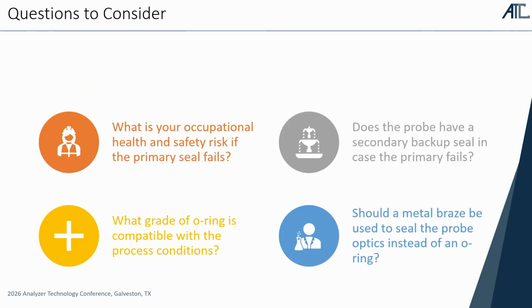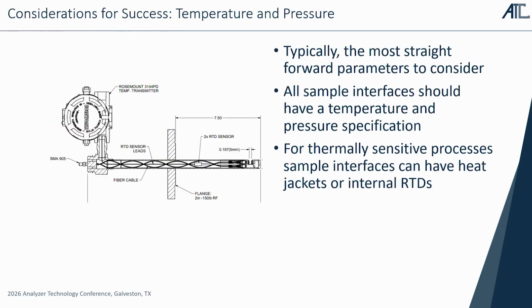But some questions to consider are like, what are the occupational health and safety risks if those seals fail, right? Does a probe have a secondary seal so if we do get a leak somewhere because we messed up and we picked the wrong O-rings, we put Viton O-rings in and we should have had Kalrez 7075 O-rings, what happens? What grade of O-rings do we need to have? Can I get away with a metal braze to seal the glass optics to the rest of the probe? Do I need the O-ring seal? Do I need something else? So these are some very basic, simple questions to make sure you're setting your specifications correctly.